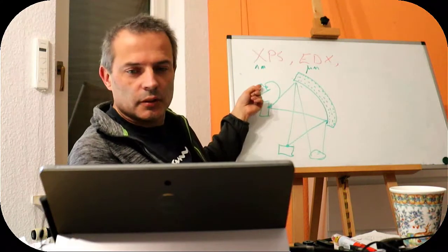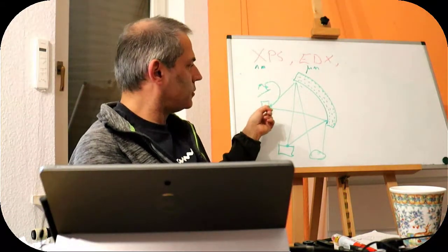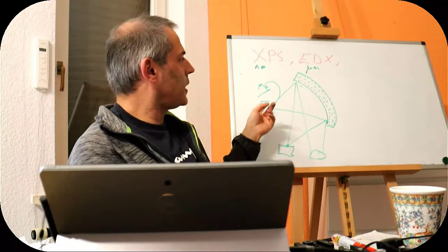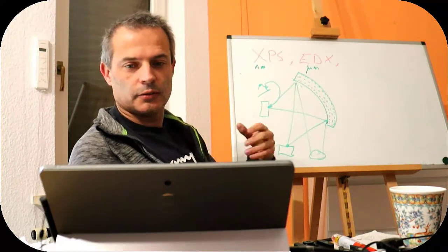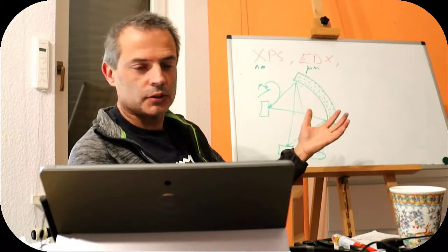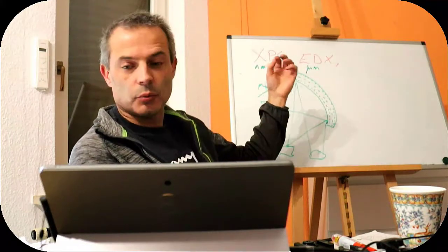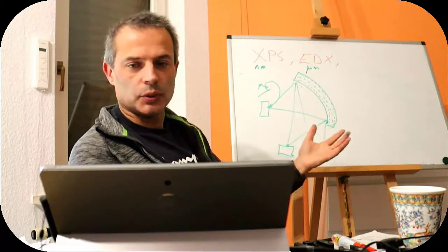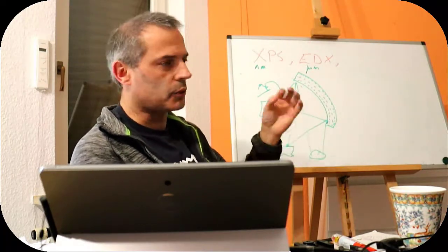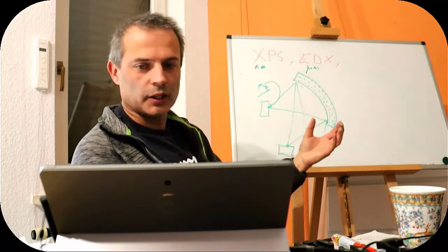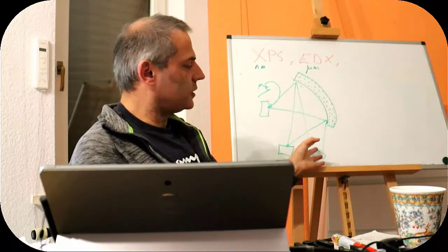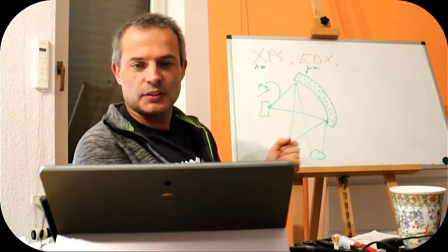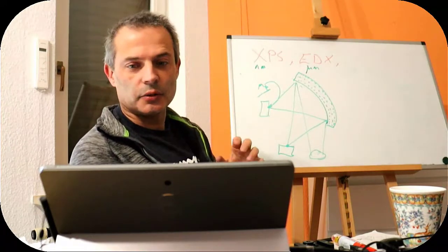We've got our filament, electrons come out, we bend them round and hit them into our anode, which generates X-rays, and the X-rays go and hit our curved diffraction grating, which is a crystal, and the ones that we want go to our sample, and the ones that we don't want, typically the other bands, but also the general X-ray background, go somewhere else where they are disposed of. That's the ideal case. Now we've got to get to the next stage.